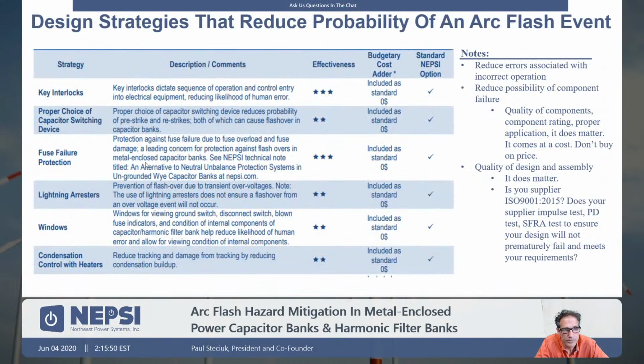So we also look at ways to reduce the probability of faults, and some of these are operational. Key interlock systems, for instance, dictate a sequence of operation. They dictate when you can go into the enclosure and when you cannot. So it's an important matter. All of our banks get key interlock systems as standard. It determines when you can get in and how you switch. It determines when you throw a ground switch and when you cannot. So we do not have people making mistakes. The key interlock systems dictate the sequence of operation.